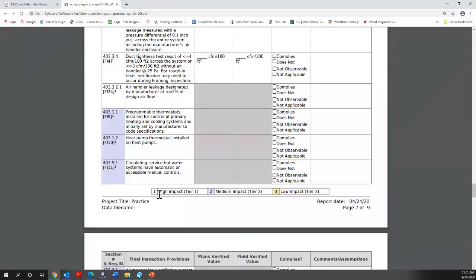Slab edge insulation, many times they'll put in that the slab's insulated because it lets them pass. But when you look at the construction documents, they have absolutely no intention of insulating the slab. And so that probably is another biggie that I see on RESchecks. And Shauna says, I find that people put an R2 or something in continuous insulation, even if they're not doing continuous, because they are counting for assembly materials, but the software already does that. He's absolutely correct. And you'll see an R1 maybe or an R2 at times on the above grade walls. And they're like, well, there's no continuous insulation. And then they come back with something like, well, the siding has an R value and my OSB and the drywall. Well, sure it does.